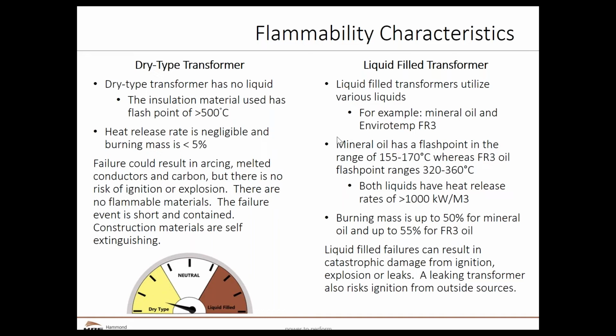Liquid filled transformers, the liquid typically can provide additional burning mass, and it can be significant. Now, modern liquids tend to have incredibly high flash points, 155, 170 C. Some of the ester oils are double that. However, in the event of a building fire, those liquids can still provide burning mass. They still have to be contained in the event of a leak. So liquid-filled transformers have a potential for catastrophic damage during ignitions or leaks.